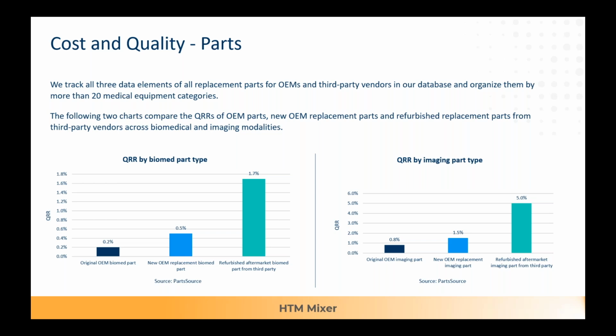Now, as you can see, if you're looking just at OEM versus replacement, there is a 0.3% difference in the quality return rate. So one extra return out of every 200 items you purchase. On imaging, 0.7% difference across the board. So for me, when I was an HTM leader and I was ordering parts, 0.3, that's nothing. That's really not that impactful overall. But you have to measure that against the savings.